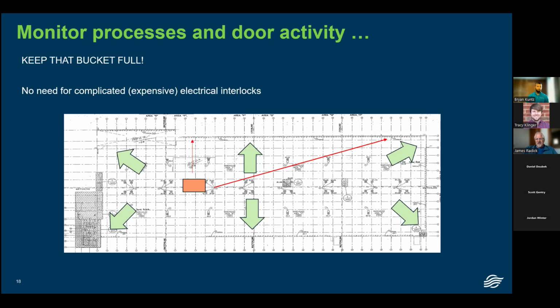Great. One would think, well, okay, it's easy enough to monitor that, but what about that exhaust process, the other arrows that are showing way, way down? It doesn't matter how far away it is. It allows you to use the building as, sometimes think of it as, a pneumatic. Pneumatics were the rage for many, many years about controlling dampers, controlling many, many things. Well, just think of the building under that slight positive pressure as being pneumatically interlocked. If a door opens quite far away from the air handler, your overall pressure in your space is going to drop. And the units themselves are equipped with an indoor and an outdoor pressure sensor, reading that differential and striving to maintain it. It'll modulate its dampers for outside air and return air to bring the right mix to provide that hundredths of an inch water column pressure.